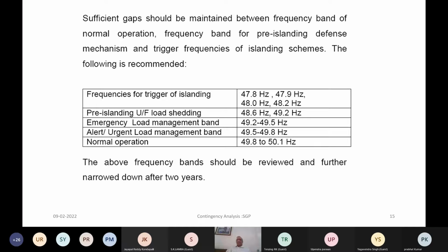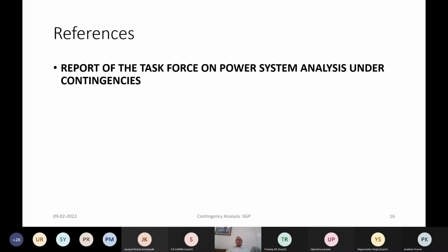These are some of the recommended settings for the under frequency load shedding scheme, and then triggering the islanding of the area. So these are the various levels at which the islanding is recommended. So this is actually a summary of the report of the task force on the power system analysis under contingencies.